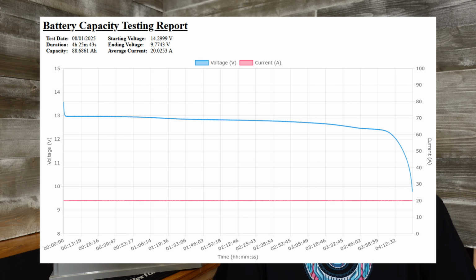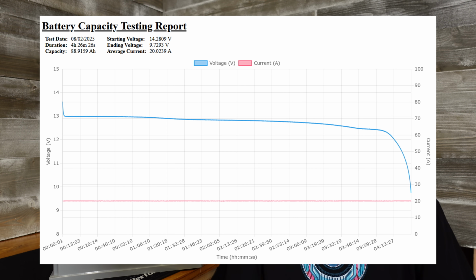Now that is quite a bit out of spec, and whenever I get an unusual result like this, I typically run a second test just to make sure it's not a mistake on my part. So I ran a second capacity test and that came back at 88.9 amp hours - fairly consistent with the first result, which is not good.